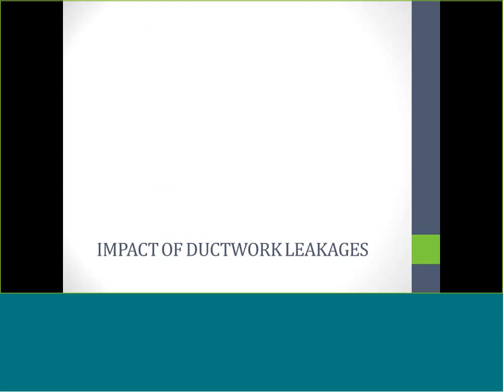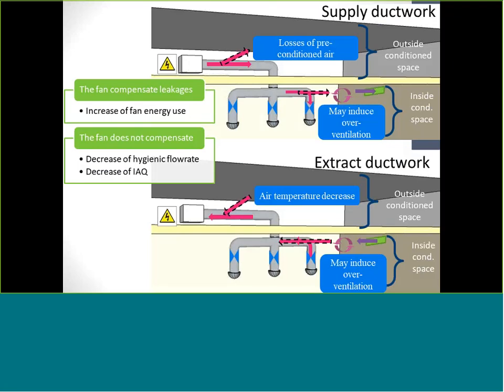So what is the impact of ductwork leakages? In fact, the impact of ductwork leakages depends on whether they are in the supply ductwork or in the extract ductwork, outside the conditioned space or inside the conditioned space. Regarding preconditioned air, leakages may induce losses of preconditioned air if they are outside the conditioned space. Also, it may induce overventilation, or in the extract ductwork, an air temperature decrease if there is leakage outside the conditioned space. Regarding the fan energy use, in fact, two things may happen.